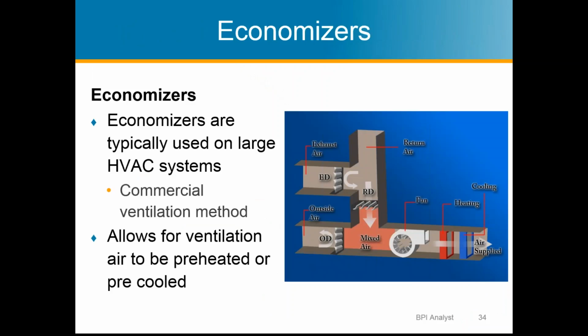And just going to talk on economizers. Economizers are really for commercial, but I just want to bring it up. You're not going to see a true economizer in most residential applications, but all an economizer is, is a ventilation system that's integrated into the HVAC system. And there are whole house ventilation systems out there that are integrated into the HVAC system, much like an economizer is. They're not called economizers though. They operate under a similar principle.